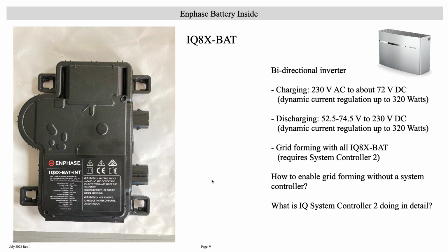The battery inverter can form a grid. I still have questions about this, especially how to enable grid forming without a system controller. I know together with the system controller it works, however the system controller is not available in Europe, and I have not seen this controller. So I'm very interested to learn what the IQ system controller is doing in detail to turn on power production here — if it's done directly via power line communication, or if there's some hidden communication which enables the batteries to form a grid. I don't know, so if you know more, put this into the comments, your feedback will probably be helpful for the community.